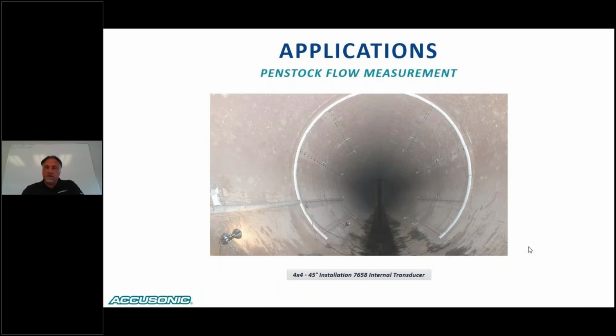This is an image of an 18-foot diameter penstock. This is an internally mounted system. It has the 7658 internal mount transducers. So they get mounted on the penstock wall. These were stud welded in place. It's a little hard to tell from the details of where the transducers are, but you can see the conduit runs coming from the upstream side to the downstream side. They get collected in a conduit manifold and then come out of the pipe through our cable penetrators.